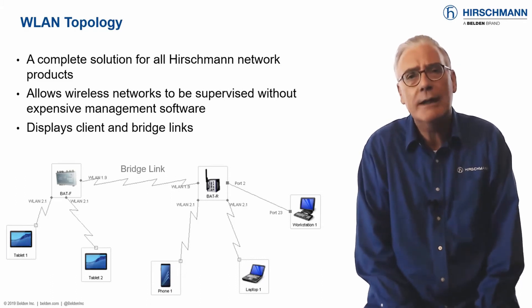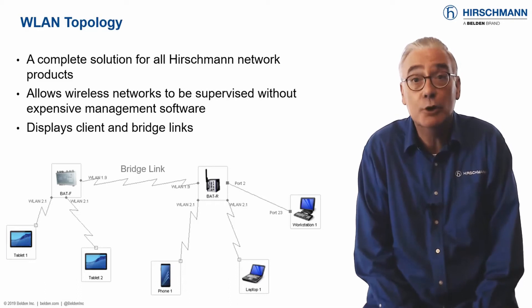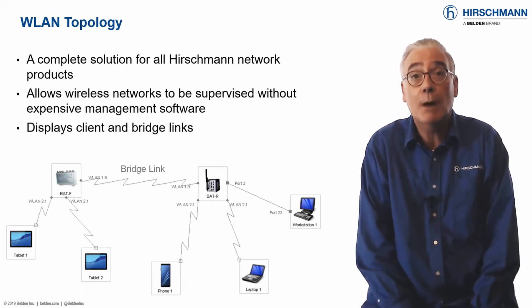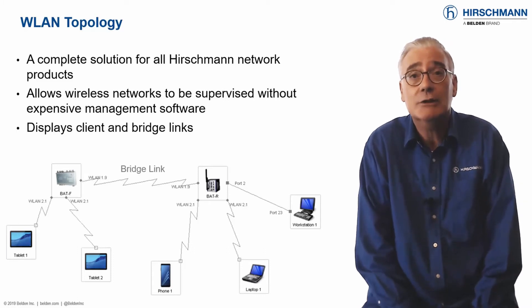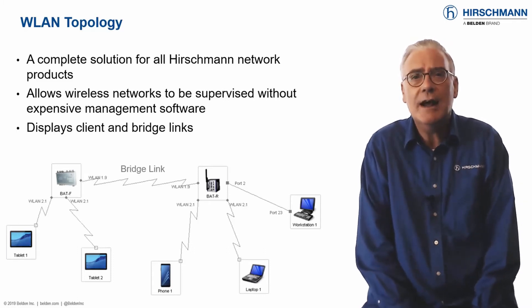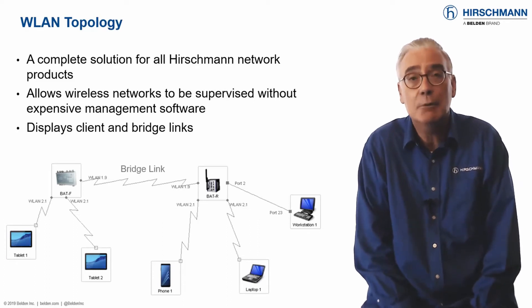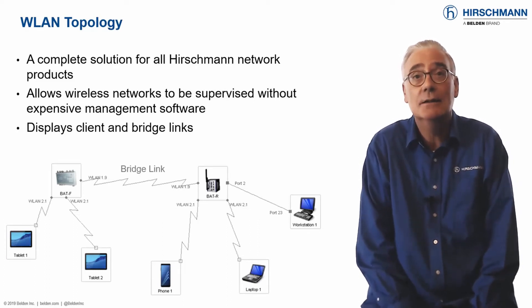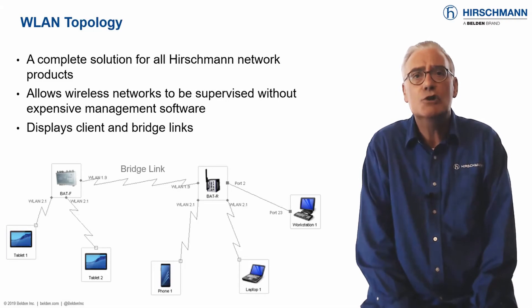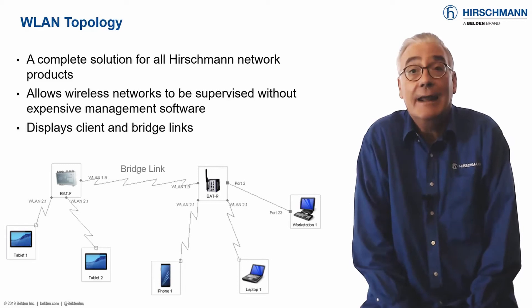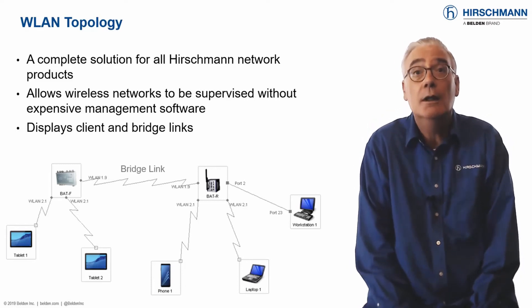Point-to-point links, also known as bridge links, behave like cables and therefore form part of the network infrastructure. Industrial HiVision uses the same display characteristics for both cabled and wireless links. So if wireless bridge links are being used as backup connections — for example in a rapid spanning tree network — they're displayed as dashed lines.